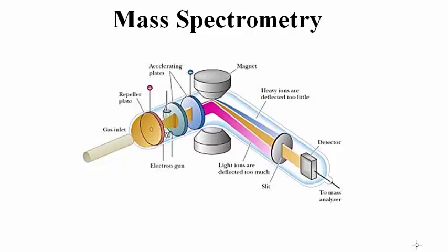This is a schematic diagram of an electron ionization mass spectrometer. Samples of gases and volatile liquids can be introduced directly into the ionization chamber. Because the interior of a mass spec is kept at a high vacuum, volatile liquids and even some solids are vaporized. For less volatile liquids and solids, the sample may be placed on the tip of a heated probe that is then inserted directly into the ionization chamber.